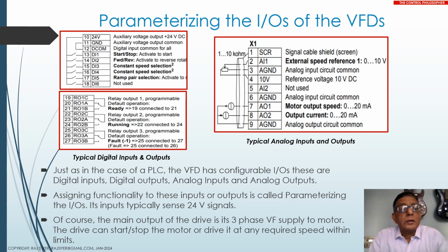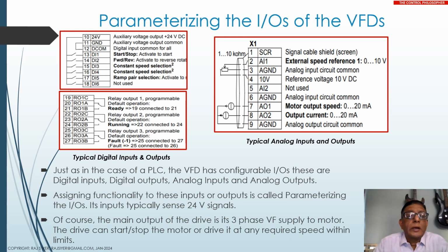For example, you look at the digital inputs. We have said that a typical input can be used for a single start-stop command or a forward-reverse command. A group of three inputs, for example DI 3, 4, 5, can be used in a combination of 3 bits, each of them either off or on, so 8 combinations of fixed speeds are possible. Sometimes you can use them to decelerate or accelerate the drive speed.